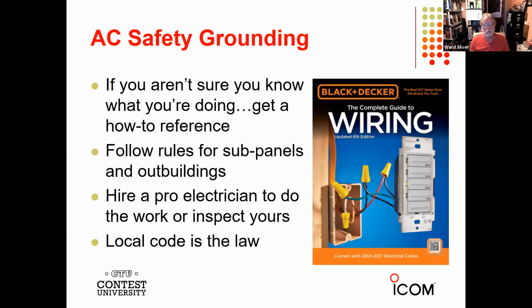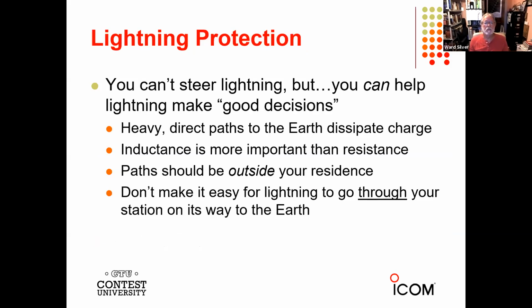So, okay, let's talk about lightning protection. You can't steer lightning, but you can help it make good decisions. Mr. Lightning comes from thousands of feet in the air, and it doesn't really care if you move things a foot apart. It's just going to jump right over it. But what you can do is help lightning get to where it wants to go, and that is to the earth. That's the whole point. By creating heavy direct paths to the earth, you allow this lightning charge to dissipate into the earth. That's what you're trying to do with lightning protection.